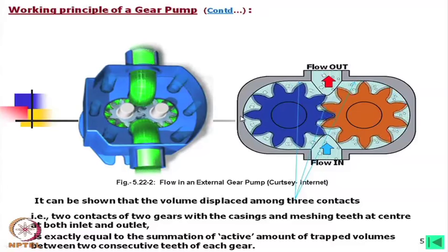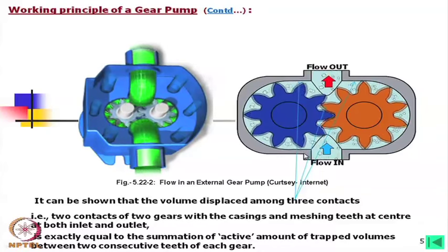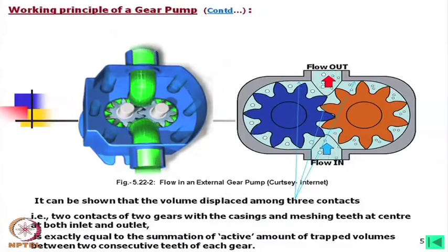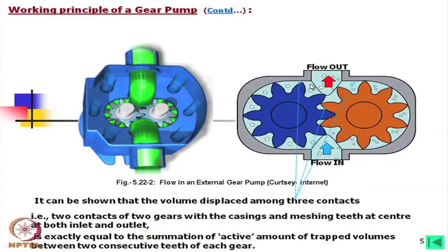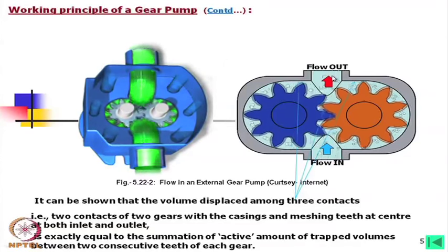Another aspect I would like to discuss: if we consider the pump, here the pressure is low — perhaps atmospheric — and here the pressure is high. If we consider the pressure curve, you can see the pressure is not increasing along the way, and then when it is exposed, suddenly the pressure increases — this is the ideal case. But what actually happens is that there is a small amount of leakage, so the pressure builds up slightly before the sudden exposure to high pressure. This causes some sort of fluid-borne noise.